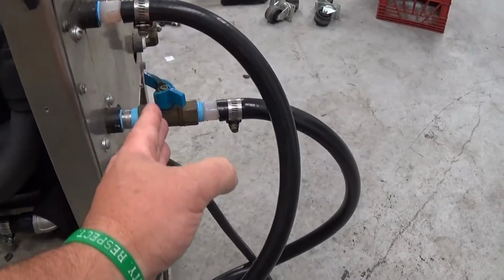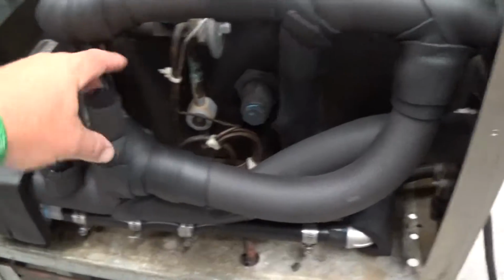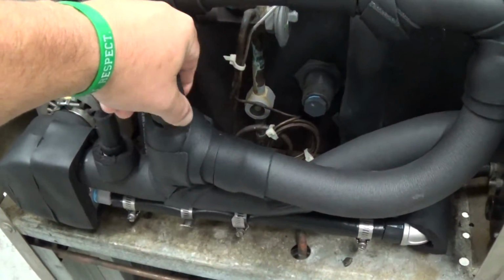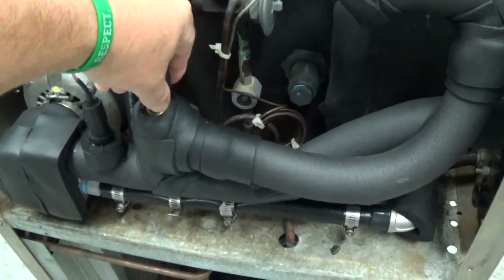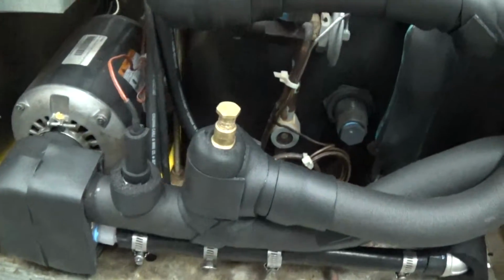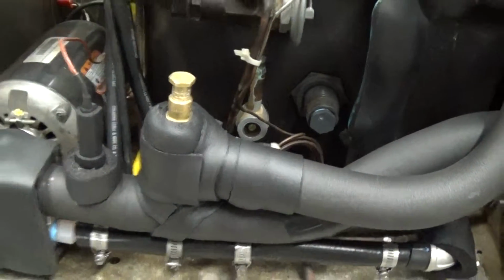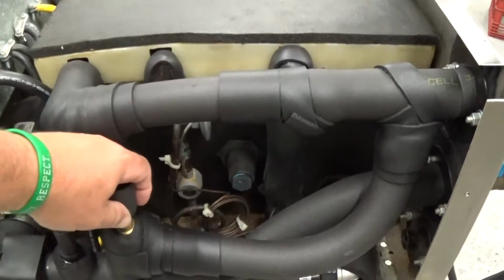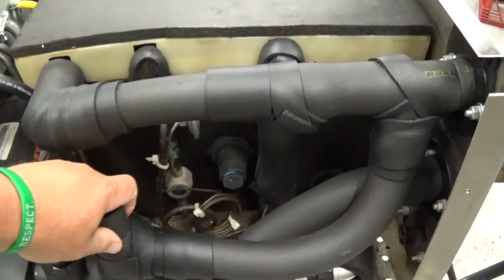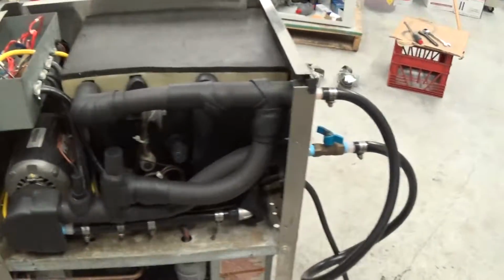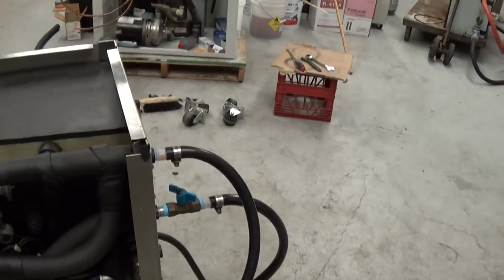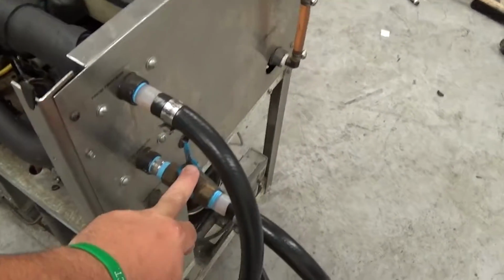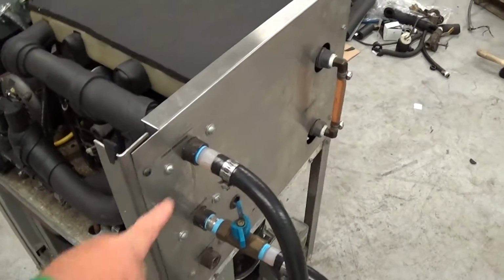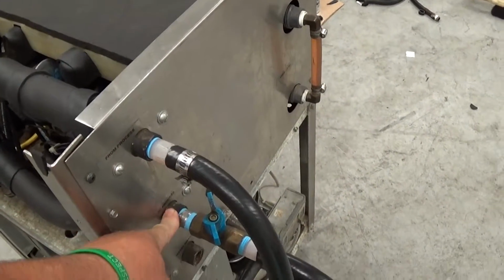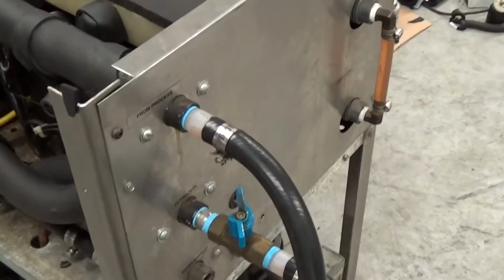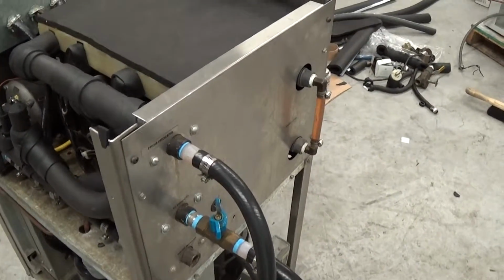You don't have to put a pipe in an additional bypass here. And our technician Dana went so far as to even insulate that. And that's your pressure regulated bypass there. And you tweak that to make sure you don't have too much pressure going out to your brewery tanks. And these are just our test fittings here. We just have a little loop. Well, I need to double check, but I'm pretty sure those look like 3/4 inch NPT connections there.